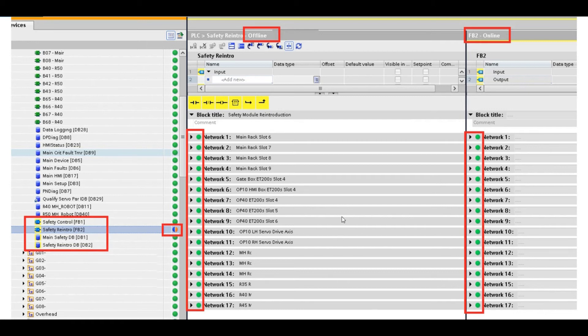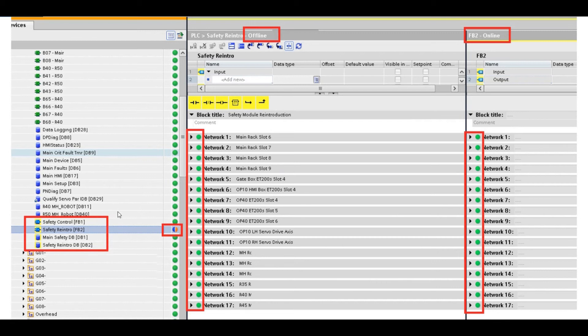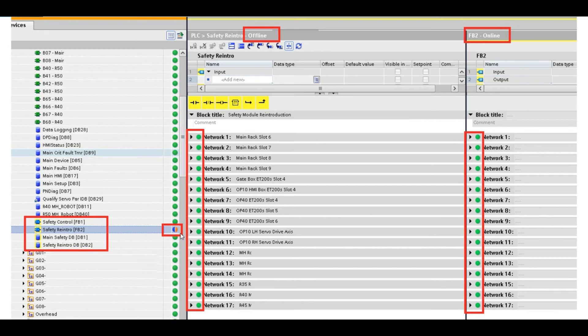The safety found the difference even if the logic never got changed. That means if your safety logic uses some tags or signals that come from the standard PLC, but you change something in standard DB, and after you compare, even if there's no safety logic change, after you download the standard logic, that safety will show the difference. Unless you download the safety logic, this difference will always show here.